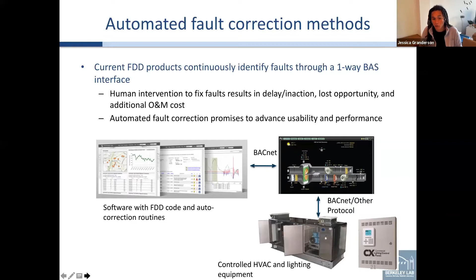We have a few steps: developing a library of automated fault correction routines, which is the engineering logic to take corrective action once a controls-related fault is identified. We're working with partners who provide FDD product to the market for them to integrate these routines into their commercial offerings, and then field testing and documenting the findings—does it work? Have we screwed anything up in trying to correct problems in the field?